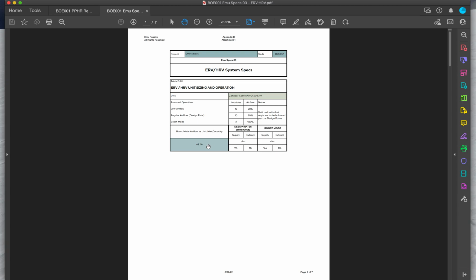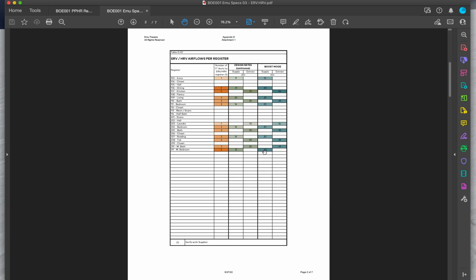And this is a check that we do. If your unit has a maximum 200 CFM, cubic feet per minute, capacity, and your boost mode rate here is 160 CFM, you don't want to choose an ERV that at the maximum can only get to 160 CFM, because it will be running at 100% capacity, so it's going to be noisy. So the percentage is a check that we do on our own work, to see what this spec rate is compared to the maximum capacity of the unit.